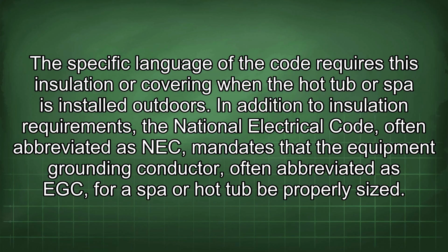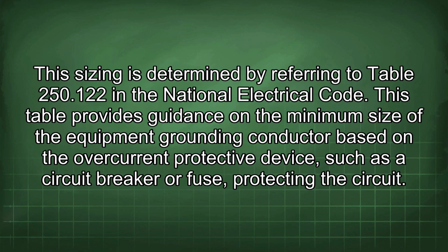In addition to insulation requirements, the National Electrical Code, often abbreviated as NEC, mandates that the equipment grounding conductor for a spa or hot tub be properly sized. This sizing is determined by referring to Table 250.122 in the National Electrical Code. This table provides guidance on the minimum size of the equipment grounding conductor based on the overcurrent protective device, such as a circuit breaker or fuse protecting the circuit.